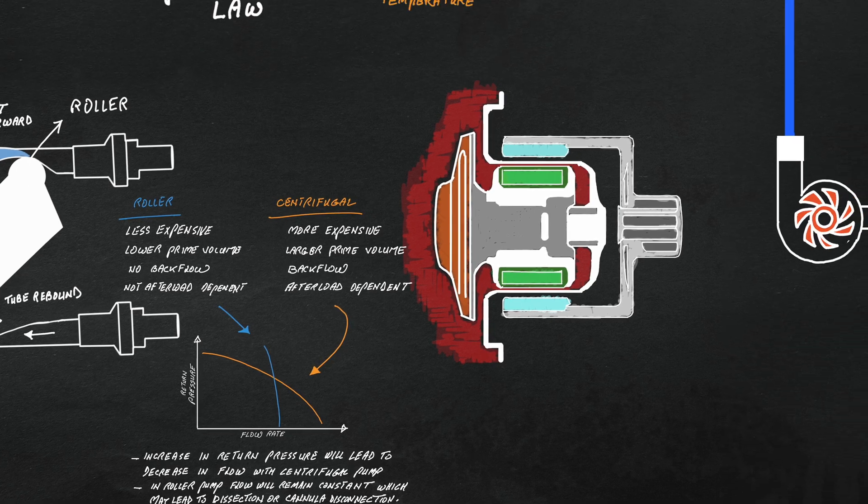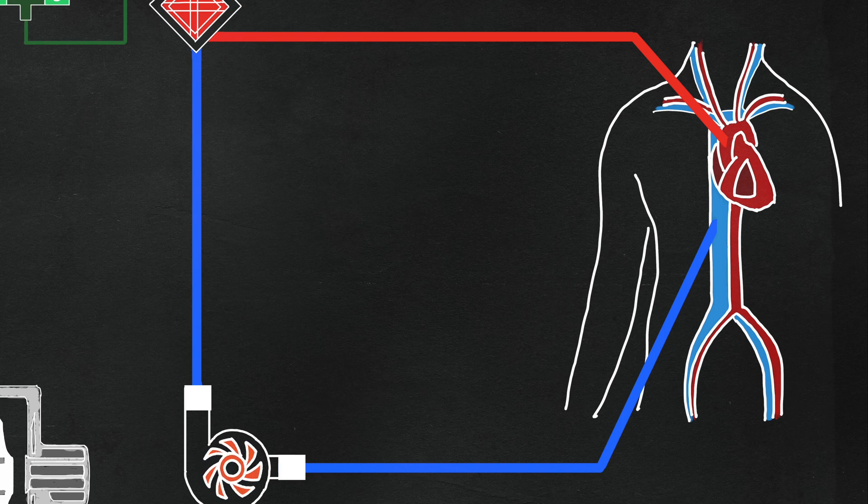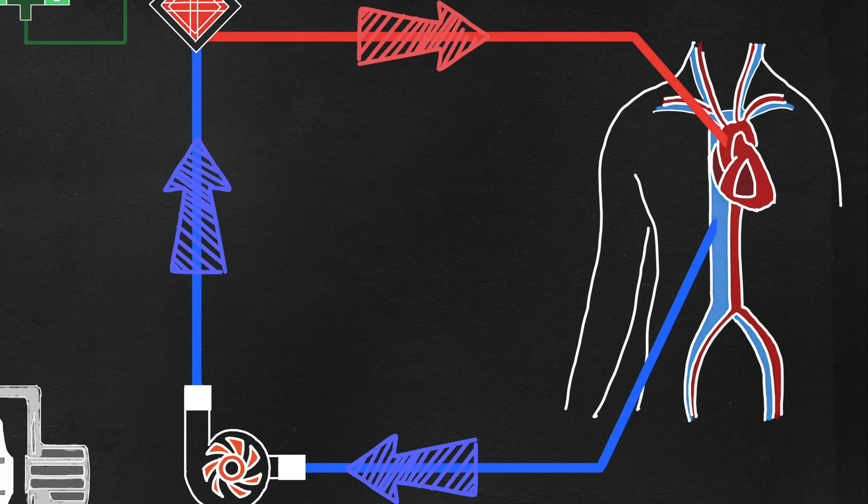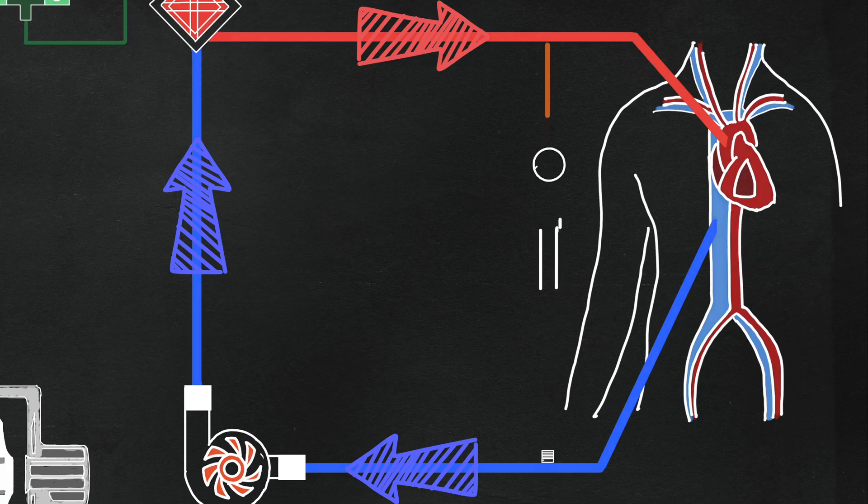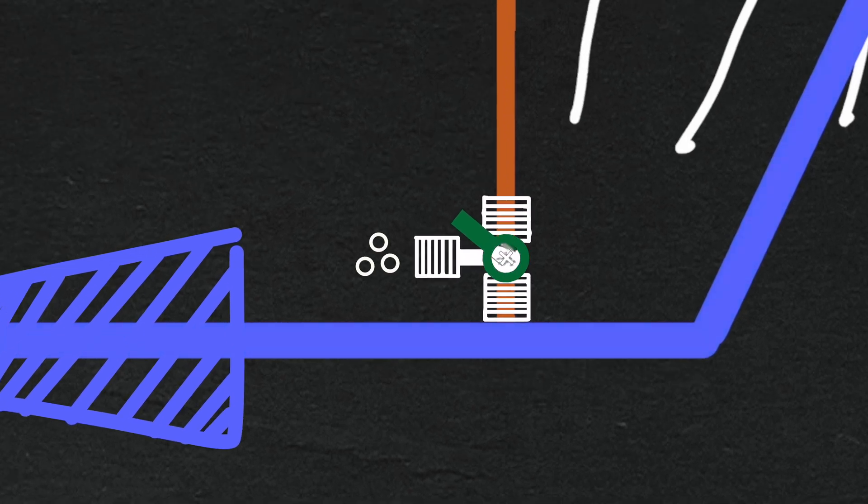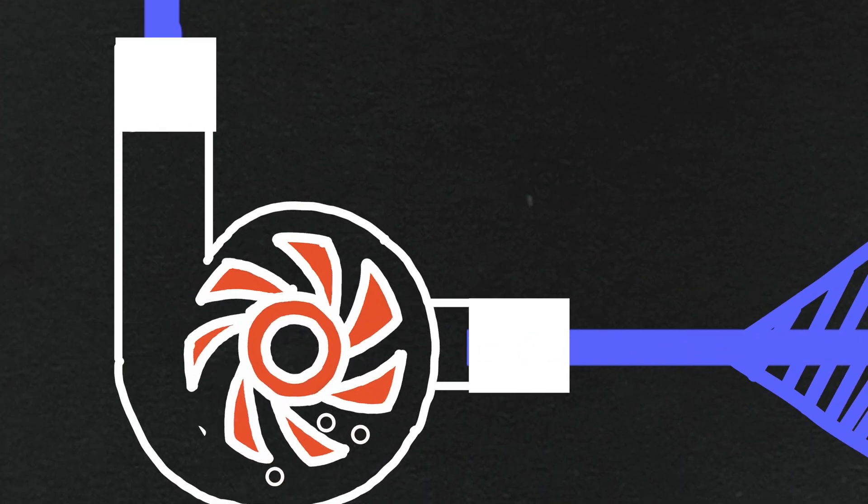Unlike bypass machines, ECMO circuits do not have venous reservoirs, which results in an increased risk for air emboli. Therefore, it's very important to take precautions during the process of hooking up the dialysis machine to the ECMO circuit. You may want to reduce ECMO flow for a short time to minimize negative pressure in the venous cannula and help minimize the risk for air emboli during dialysis machine connection to the circuit.